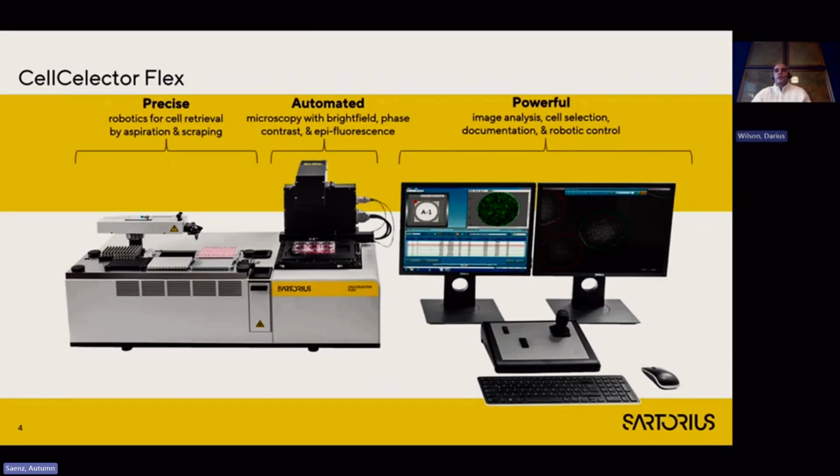So you're identifying the organoids you want to be picking. Let's say you want to have 96 organoids with 80 microns in diameter and perfectly spherical. You put this into your image analysis workstation. The instrument will then identify exactly what organoids you have in your source plate, pick them, and then transfer them.